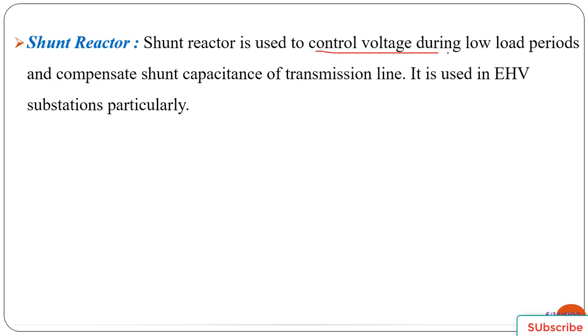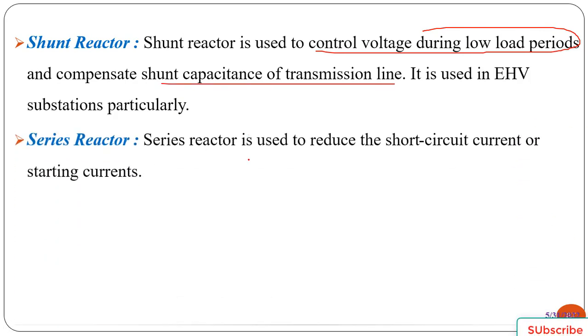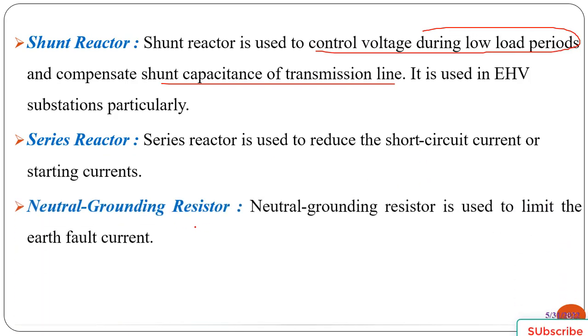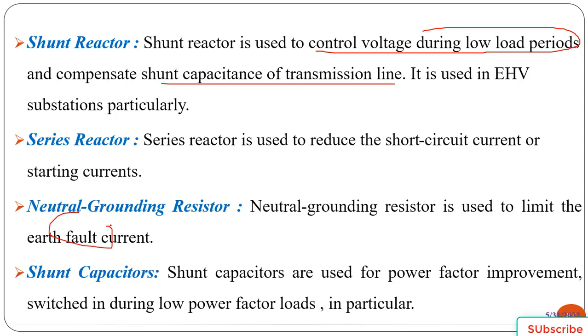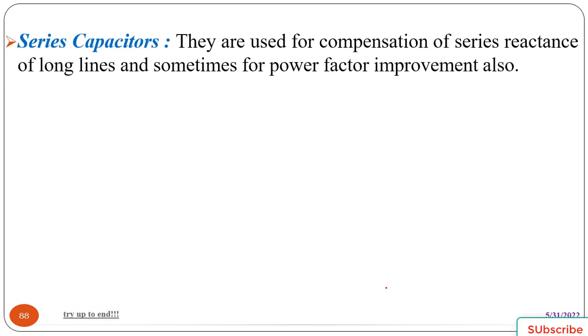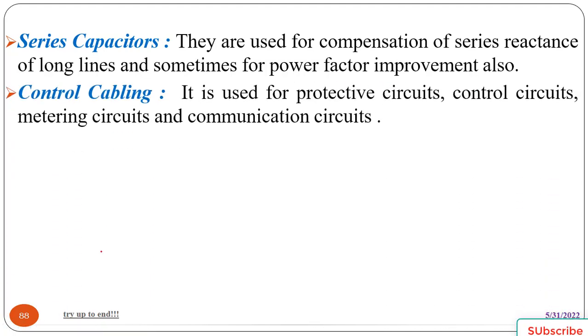The next one is the shunt reactor, which is used to control voltage during low load periods and compensate the shunt capacitance of the transmission line. It is used particularly in extra high voltage substations. Series reactors are used to reduce the short circuit current or starting current. Then the neutral grounding resistor is used to limit the fault current. And the other main components in a substation are shunt capacitors, which are used for power factor improvement and switched in during low power factor load in particular. The other is series capacitors, which are used for compensation of series reactance of long lines and sometimes for power factor improvement also.